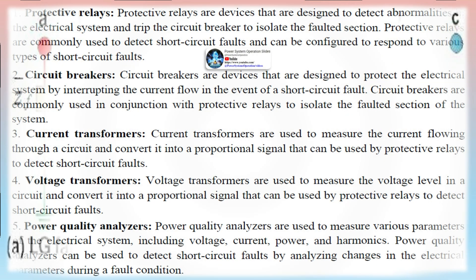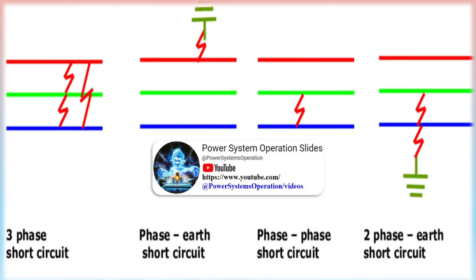Power quality analyzers are used to measure various parameters of the electrical system, including voltage, current, power, and harmonics, and can detect short-circuit faults by analyzing changes in electrical parameters during a fault condition. Fault locators are devices used to locate the exact location of a short-circuit fault in the power system, using techniques such as time domain reflectometry and impedance measurement to locate the faulted section.